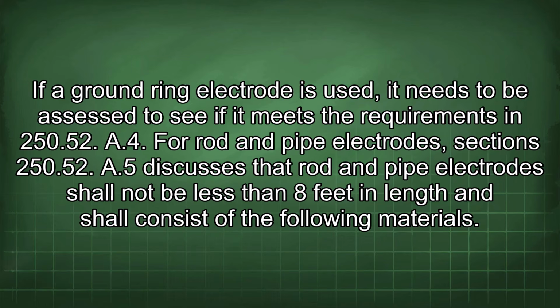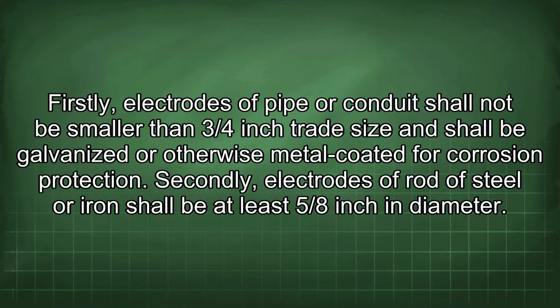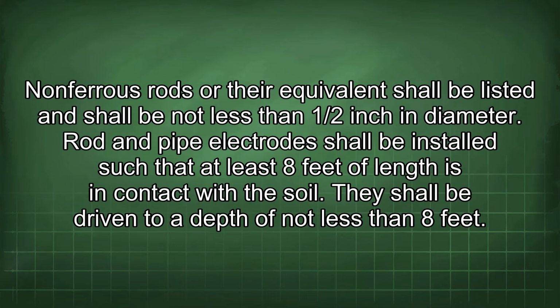(A)(5) discusses that rod and pipe electrodes shall not be less than 8 feet in length and shall consist of the following materials. Firstly, electrodes of pipe or conduit shall not be smaller than 3/4 inch trade size and shall be galvanized or otherwise metal coated for corrosion protection. Secondly, electrodes of rod of steel or iron shall be at least 5/8 inch in diameter. Non-ferrous rods or their equivalent shall be listed and shall be not less than 1/2 inch in diameter. Rod and pipe electrodes shall be installed such that at least 8 feet of length is in contact with the soil. They shall be driven to a depth of not less than 8 feet.